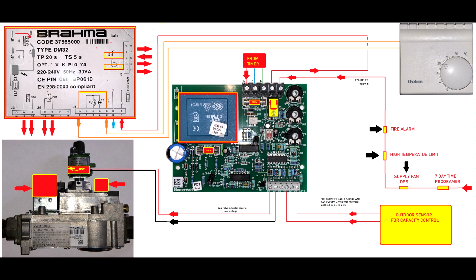So we can interrupt the signal at any point. All the alarms should be okay. You should have no alarms, or otherwise the signal will not reach this printed circuit board. If all the alarms are okay and you don't have any trouble, then the signal will reach the relay which is on the printed circuit board, and the circuit board also will be powered up because the timer will give power to both the relay and the printed circuit board. So you'll have a loop in between L1 of the printed circuit board and the relay input.